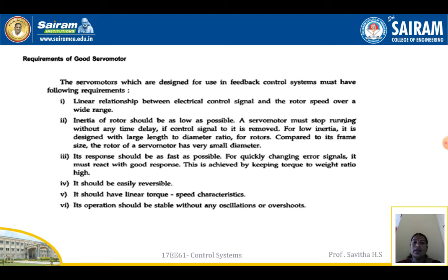For low inertia, it is designed with a large length to diameter ratio for rotors. Compared to its frame size, the rotor of a servo motor has a very small diameter. Its response should be as fast as possible. For quickly changing error signals, it must react with good response. This is achieved by keeping the torque to weight ratio high.